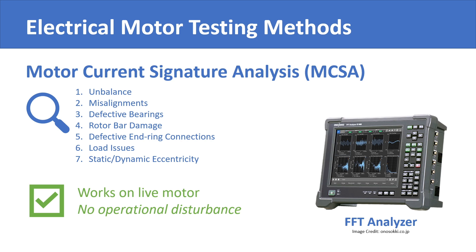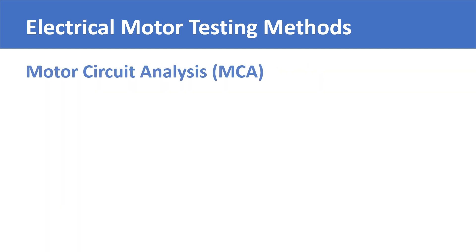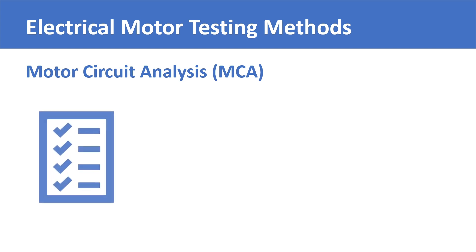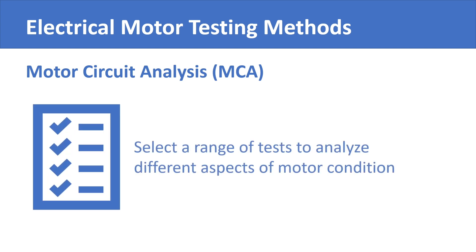Finally, a motor circuit analysis, or MCA, refers to using a range of voltage, current, and impedance tests, including the ones we have already discussed, to analyze different aspects of motor condition.